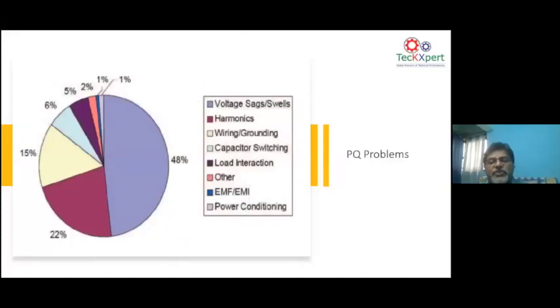Typically, power quality problems, as I explained in the previous slides, we talked about short duration, long duration, steady state, non-steady state, harmonics. Now, power quality is a sum of all this. Voltage sags and swells are voltage quality problems. As you all know, sags and swells happen when you have a short circuit taking place. Certainly, a voltage sag goes through the grid, and ultimately a consumer gets affected. Similarly, for a swell, if a ground fault happens on one phase, the other 2 phases will have over voltage. So that comes as a swell. Similarly, if there's a sudden throwing away of load, you will also have a swell.